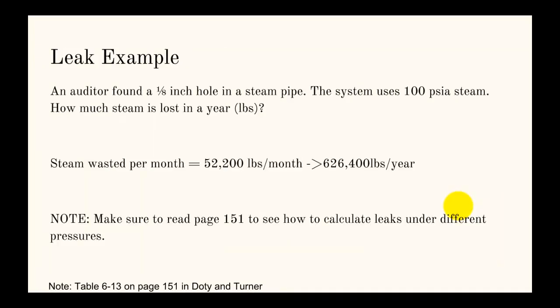Now let's go to our last example. This is just a leak example. When you find a leak in a steam pipe, and the system is using 100 psi steam, we're trying to figure out how much steam is lost in a year. The nice part is there's a nice table that does this, that shows how much steam is lost in a year on page 151 of Doty and Turner, table 6.13. It gives you the 52,200 pounds per month of steam wasted. Then you can multiply by 12 to get the pounds per year. However, this table is only for 100 psi steam. You want to make sure you read that page to figure out how you would correct if it's a different pressure steam line. So those are some of the boiler and steam calculations for the CEM.